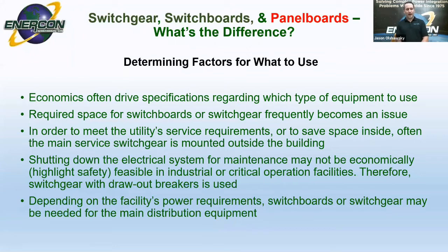Whereas if you have a draw-out breaker, it is going to have what's called a cradle, and that cradle is what's connected to the copper bus. That allows you to remove that breaker and replace it with a new one without having to go in and shut down all that bus work and make those changes that way. Depending on the facility's power requirements, switchboards or switchgear may be needed for the main distribution of equipment.